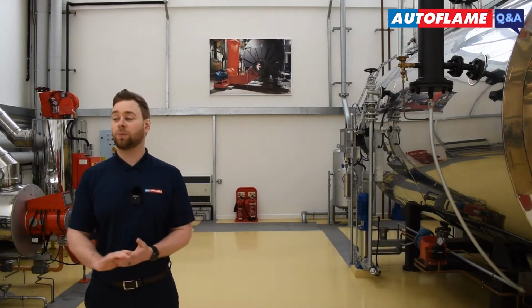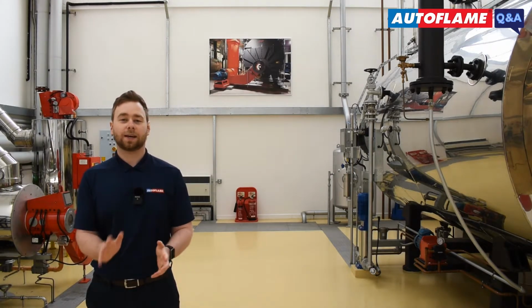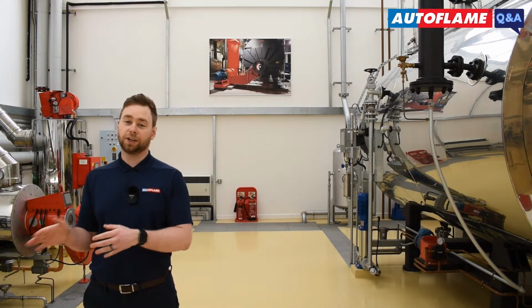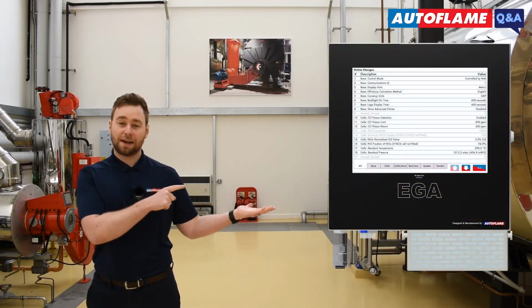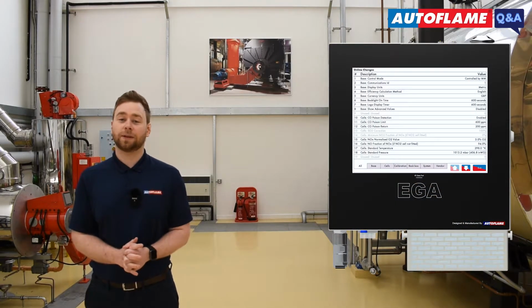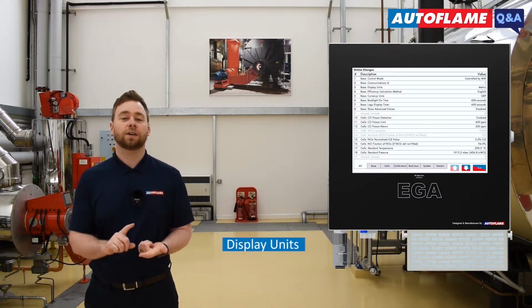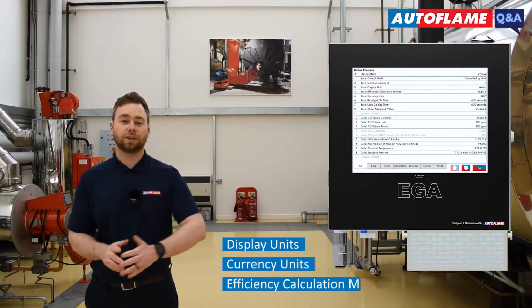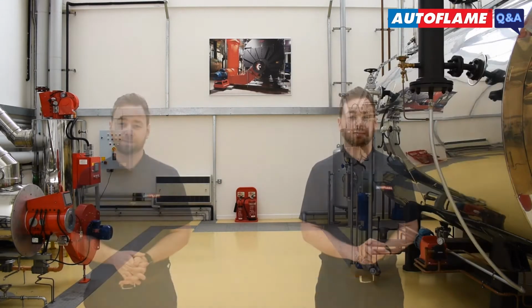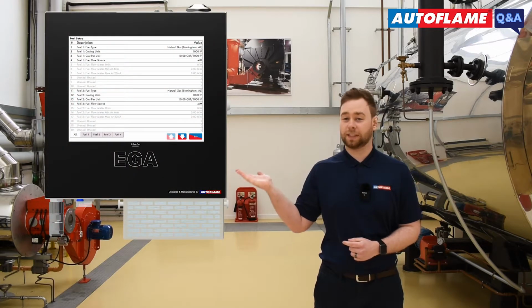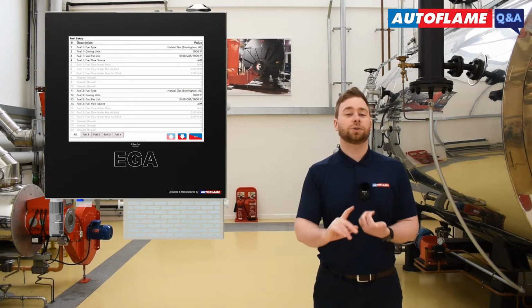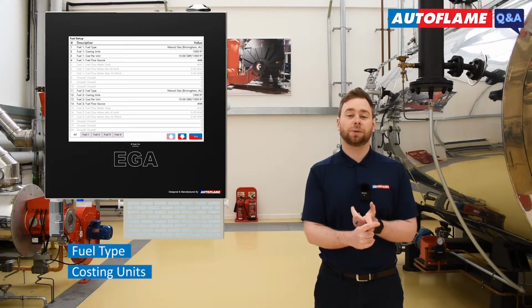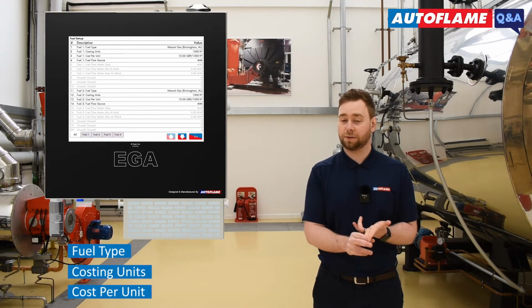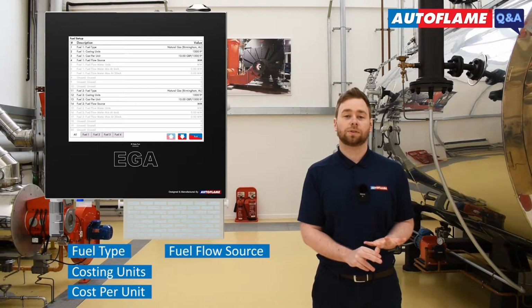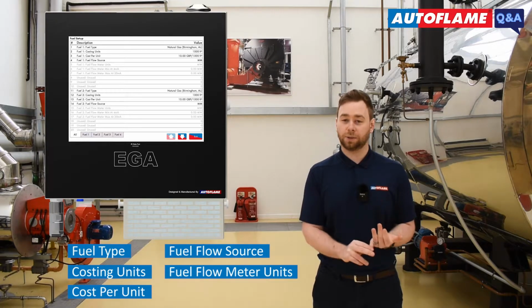Now that your flow meter has been wired directly into the EGA, there's just a couple of settings we have to configure on the EGA itself. If you navigate to your EGA settings menu, you set your display units, your costing units, and your combustion efficiency calculation type. Now you can proceed to your fuel setup screen. In here, you choose your fuel type, your costing units, your cost per unit of fuel, your fuel flow source, and your fuel flow meter units.